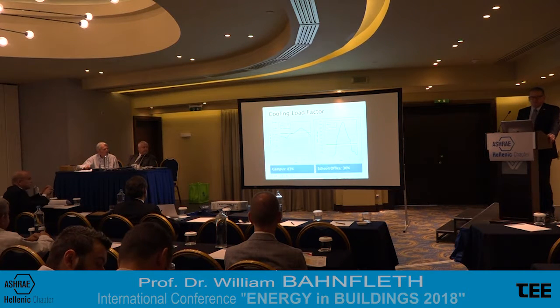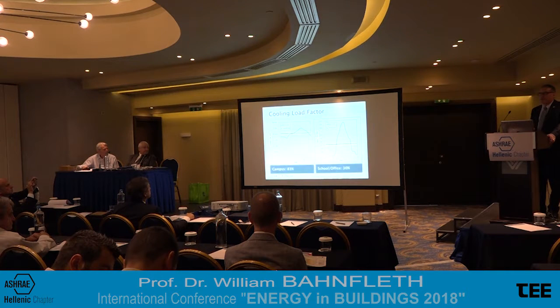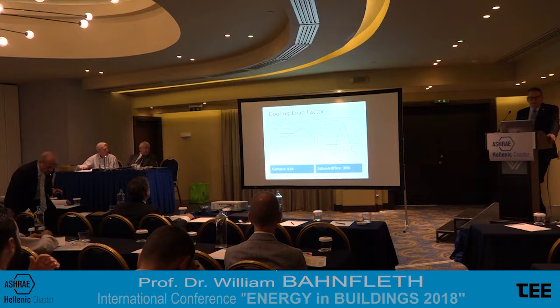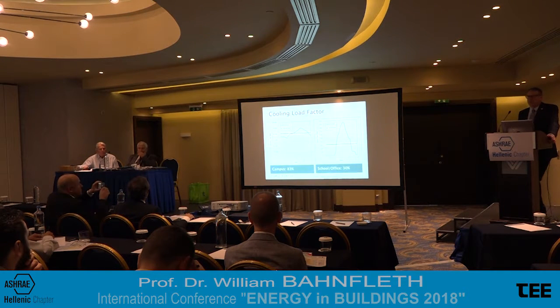Here are some examples of typical profiles for something like a district cooling system for an urban center or for a campus. They tend to have large flat loads, and the load factors are fairly high. The horizontal orange line there is the average load, and we take the ratio of that to the peak of the actual load profile, the blue line, to get the load factor that's shown. So for this one, we have an 83% load factor.